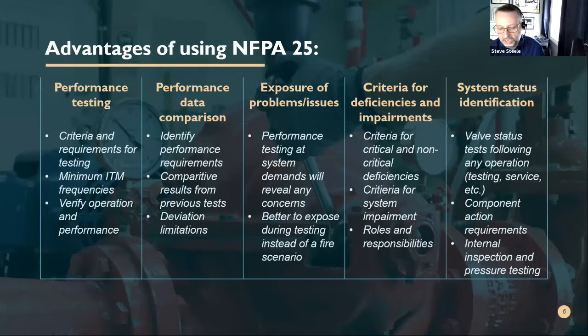It's just not a slight level. You're doing that system required. You're doing full flow tests. And again, some may fear, well, you don't want something to go wrong. Well, this is where you want it to go wrong. On the ITM, you don't want it to go wrong during a fire scenario when it's needed for the protection of the property, the life, or the fire services that are there suppressing the fire.